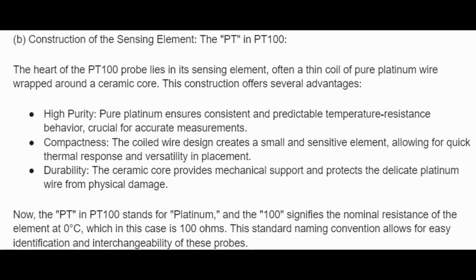B. Construction of the sensing element, the PT in PT100. The heart of the PT100 probe lies in its sensing element, often a thin coil of pure platinum wire wrapped around a ceramic core. This construction offers several advantages. High purity. Pure platinum ensures consistent and predictable temperature-resistance behavior, crucial for accurate measurements.